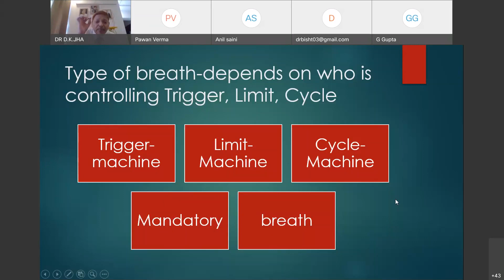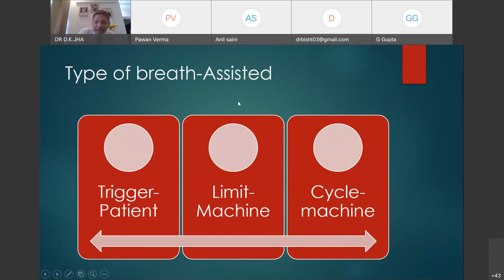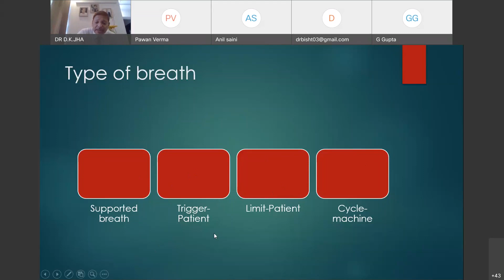The other type of breath is the assisted breath. What happens in this breath? The breath is triggered by the patient, limited by the machine, meaning the inspiratory phase is regulated by the machine in the form of pressure or volume, and cycled by the machine, meaning the inspiratory phase is terminated by the machine. So this is called assisted breath. Next is the supported breath. What is the supported breath? In this, just remember TLC. In supported breath, triggered by the patient means the breath is initiated by the patient, limited by the patient means the inspiratory phase will be determined by the patient, but cycled by the machine, the inspiratory cycle will be ended by the machine. So this is the supported breath.